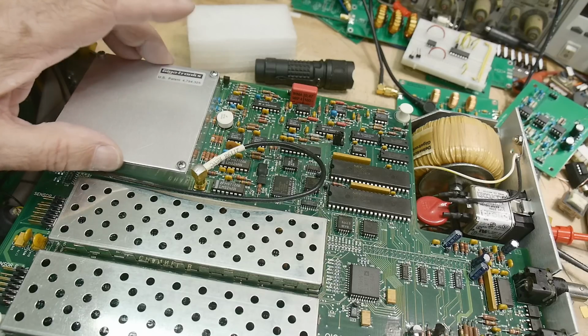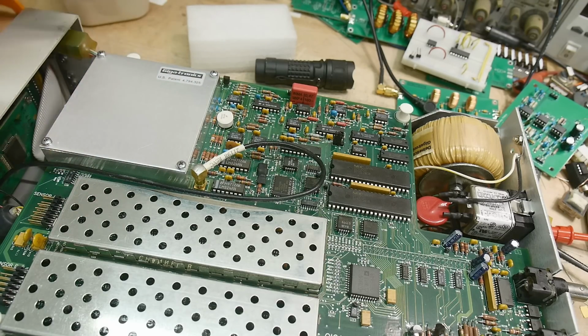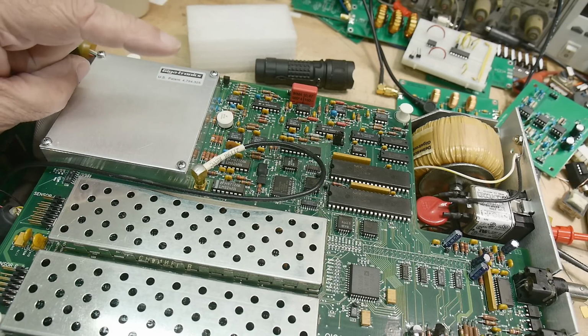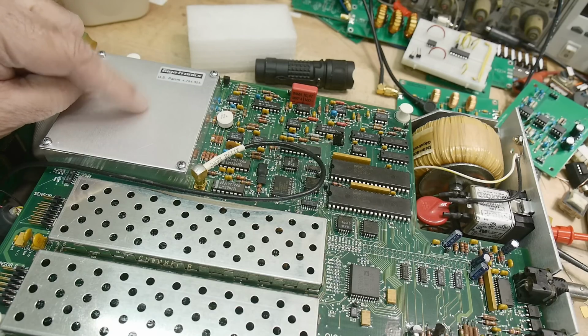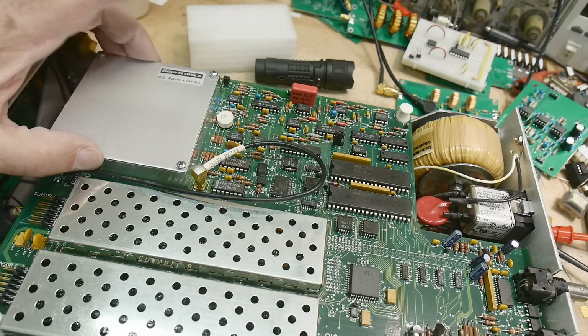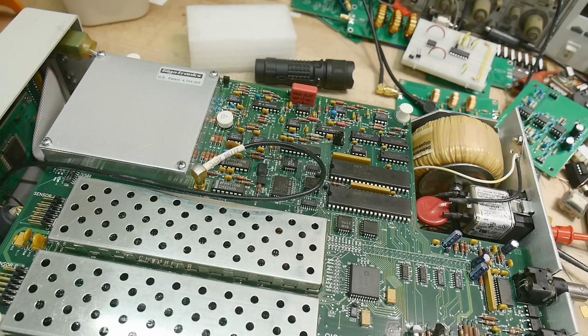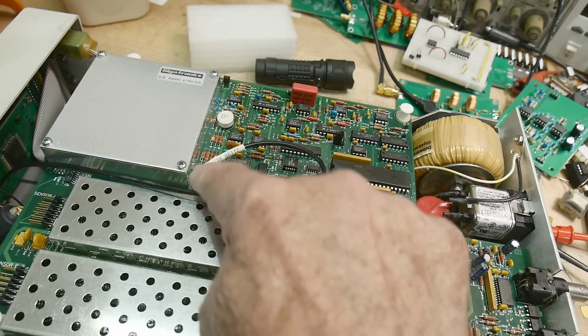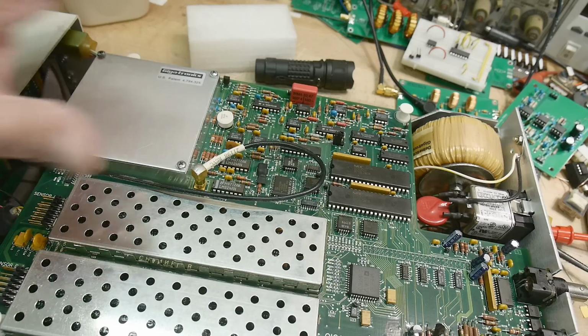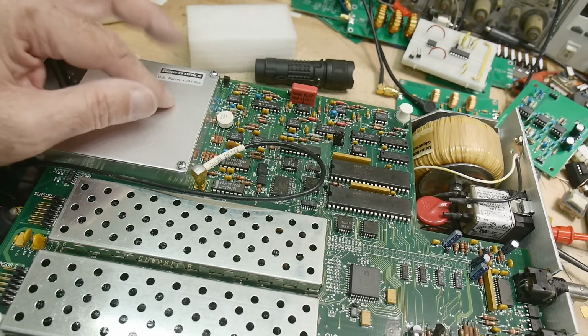All right, so we need to talk about this because this is kind of the heart of the instrument. This is where the accuracy of the instrument comes from. It has local calibration. So when you use these power meters, you put the power meter on the connector on the front. That's the cal connector. And the cal connector comes over to this box. Well, this box is a power meter inside the power meter.